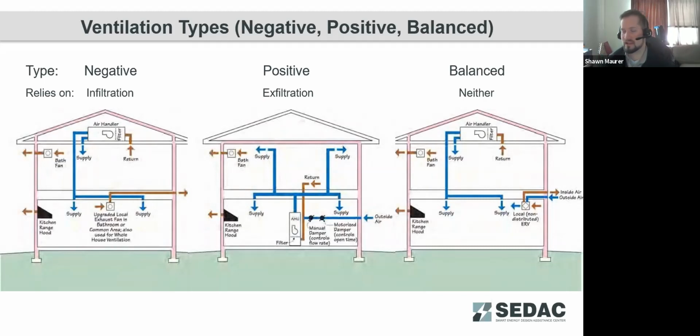And if you do have an intermittent ventilation system, which we do see somewhat more commonly, then you need to document that the ventilation airflow rate is appropriately increased so that you meet the time-average requirement of ventilation as if that system were running 24/7. So if you run one out of every 4 hours, your instantaneous ventilation rate for that fan would be four times higher than if it ran 24/7.